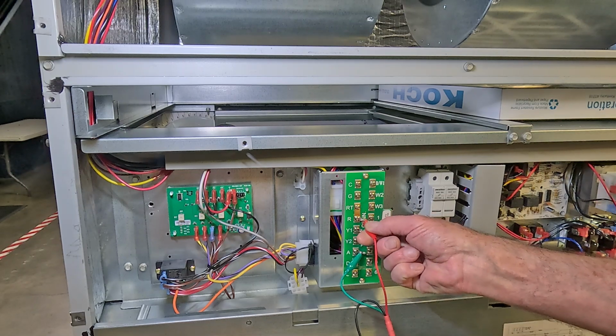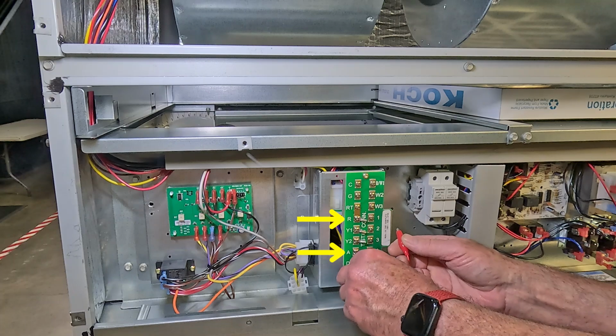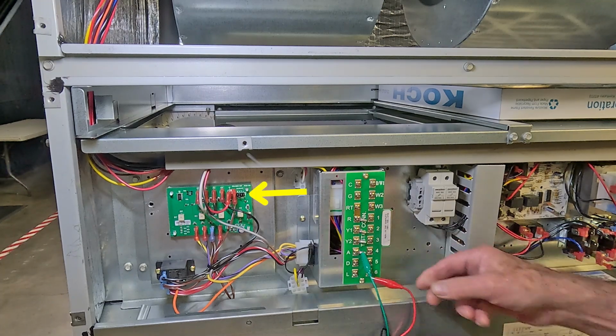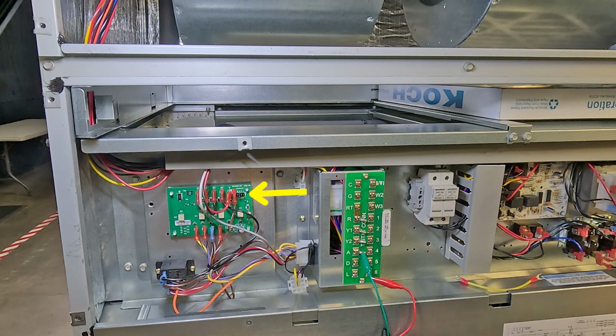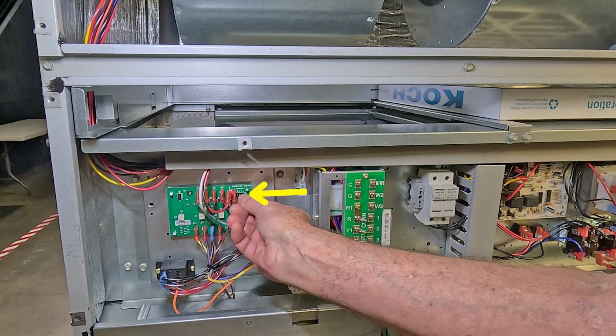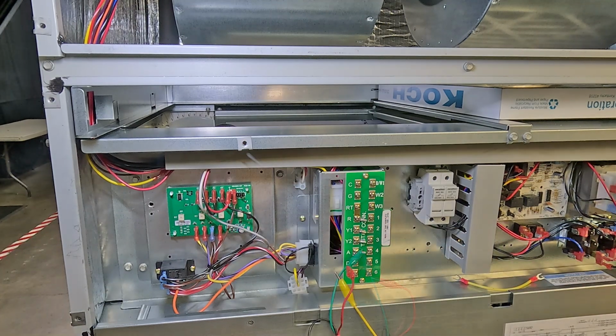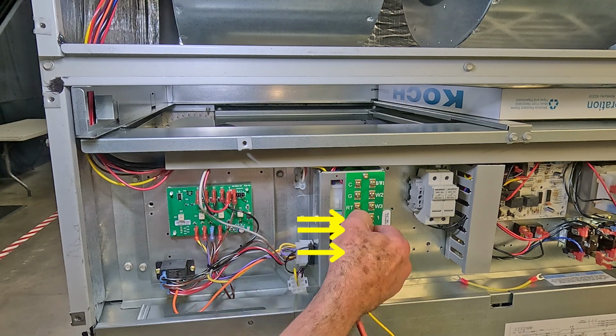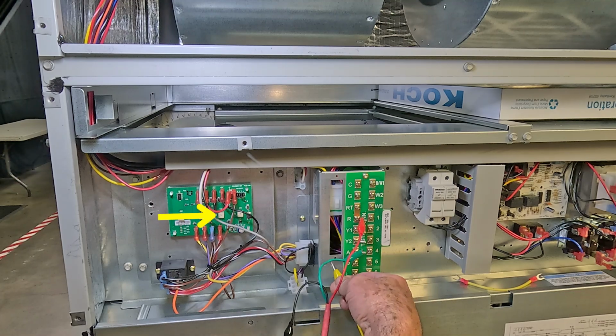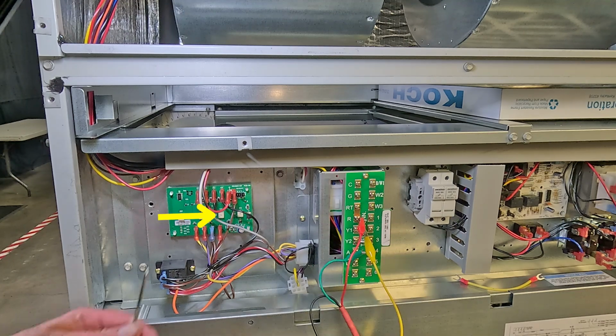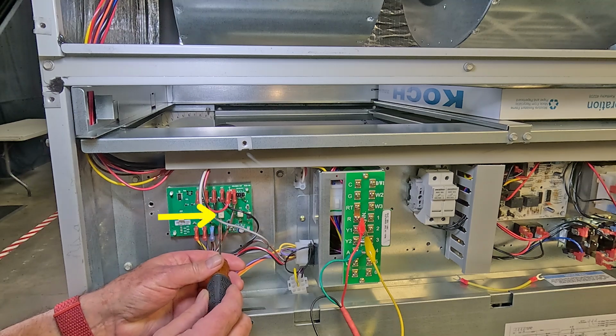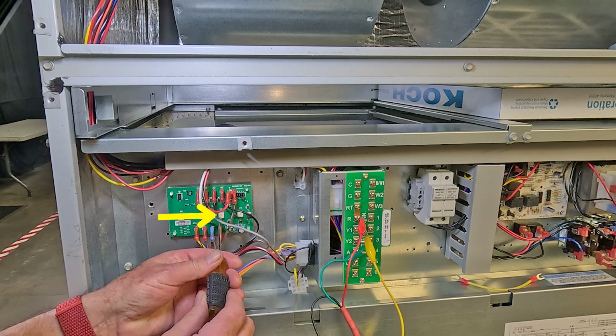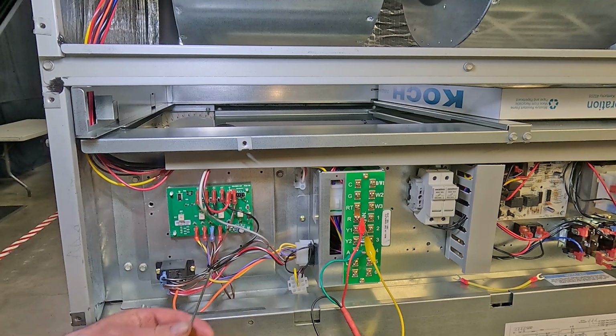Remove the jumper wire from R to A. If you do not want a pre-purge prior to your occupied setting, move the little black pre-purge jumper back to 0. On a 2-stage compressor unit, jumper wire R to A and Y1. And turn Y1 pot switch clockwise for the damper to number 7 on the decal. This compensates for the first stage blower CFM being lower than second stage blower CFM.